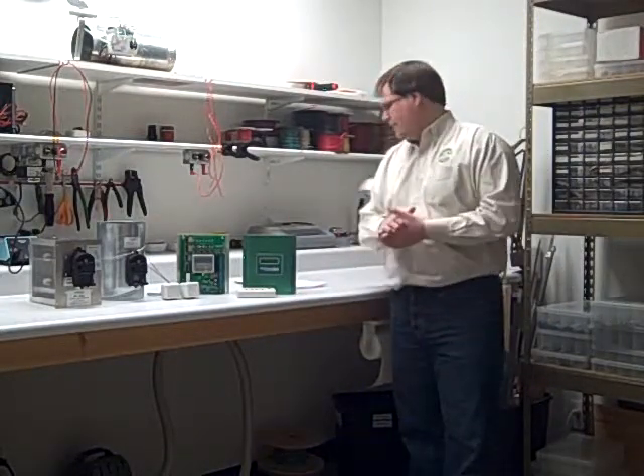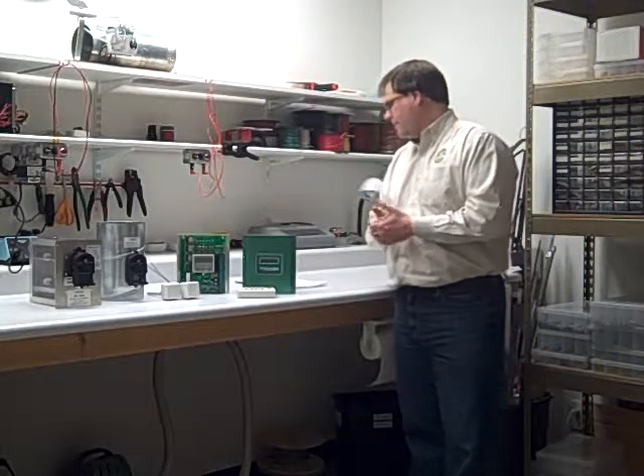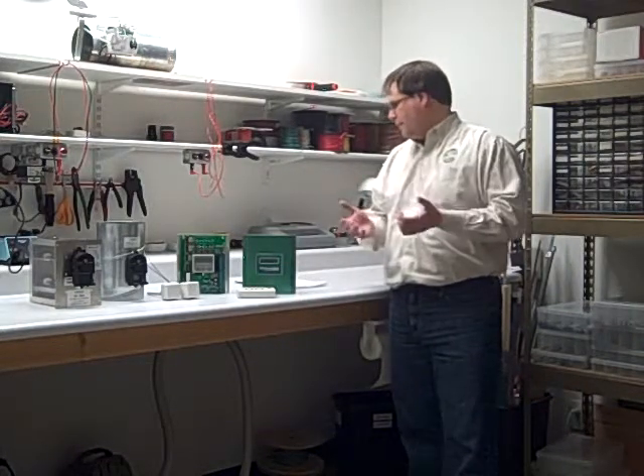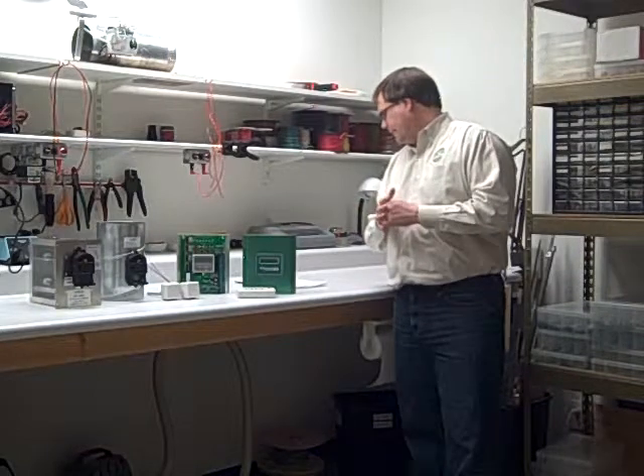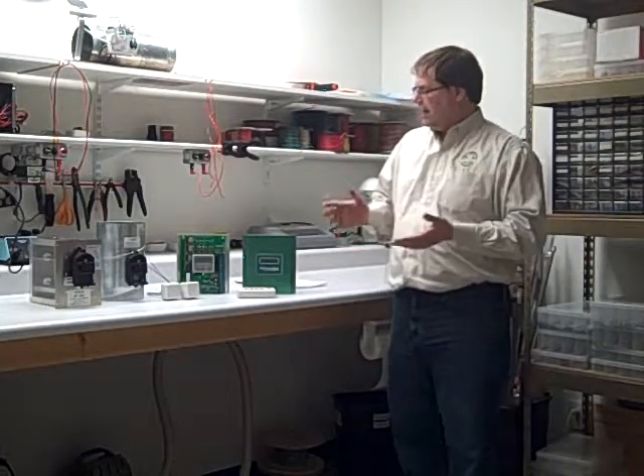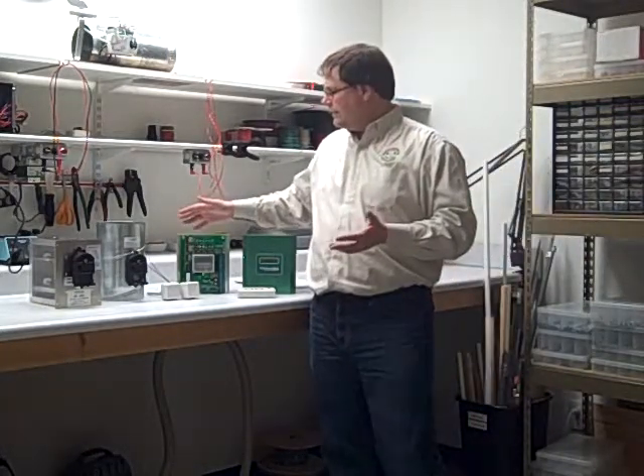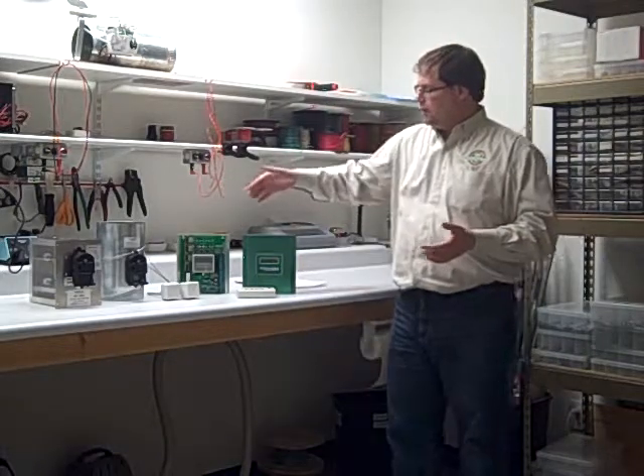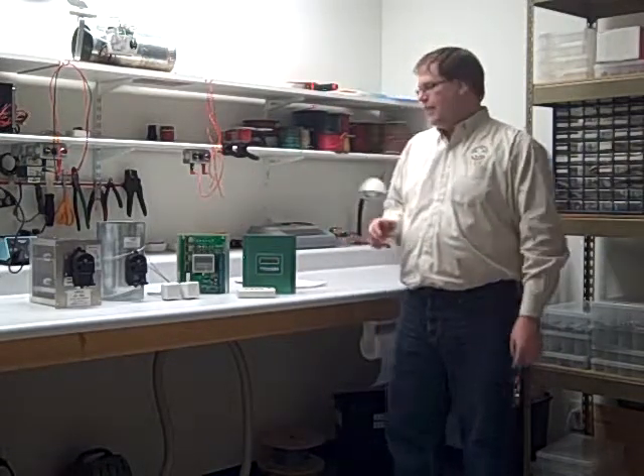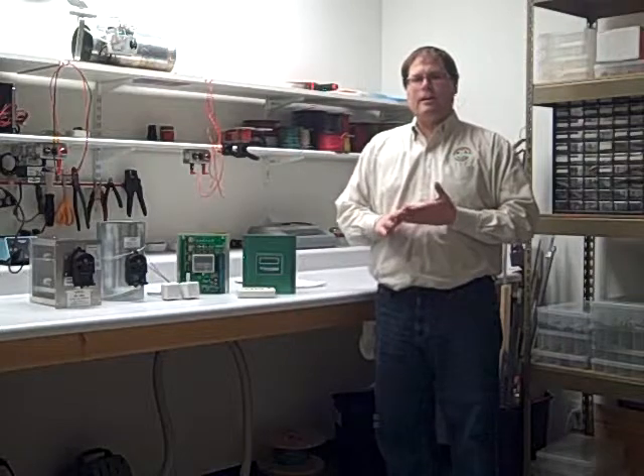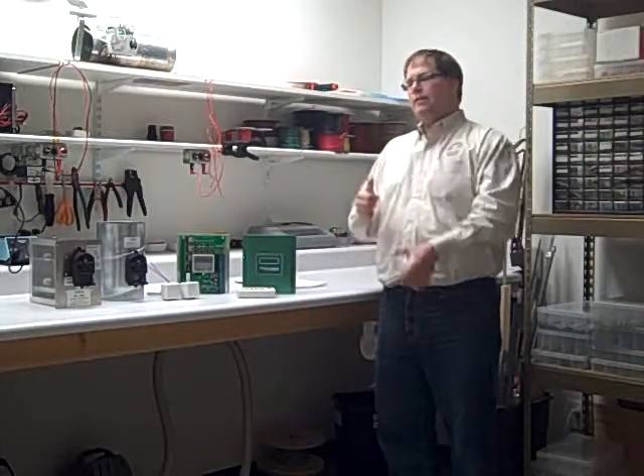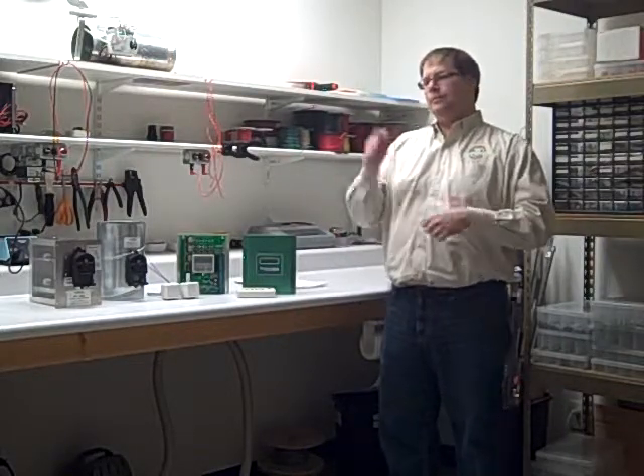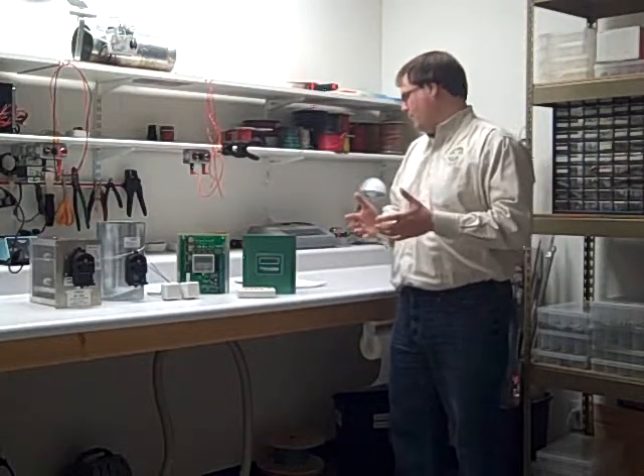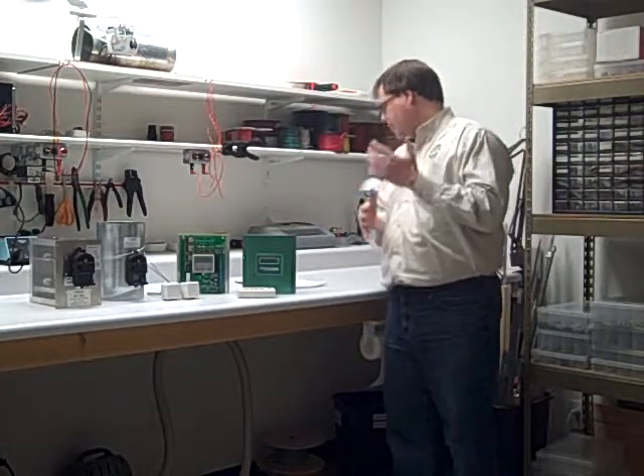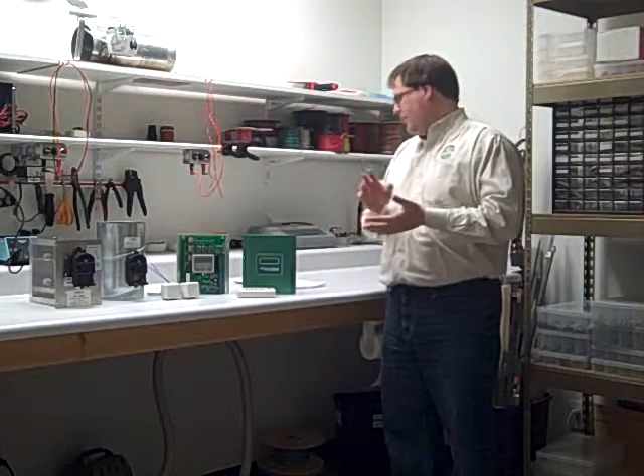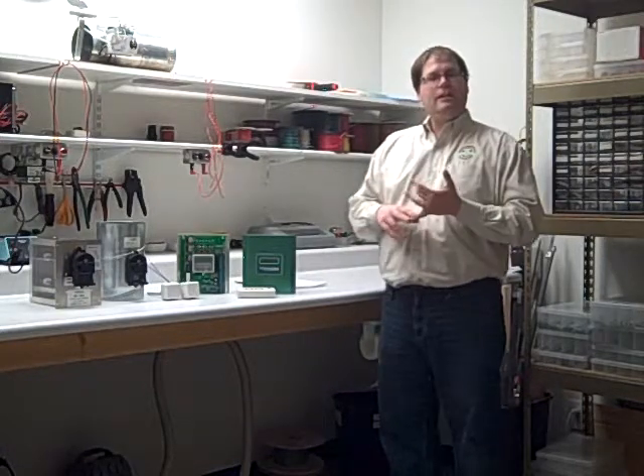We've talked about the additional safety features with the return air sensors. We've talked about fuse protection. It also has a lot of the features you know if you've used our regular Z-600. We've incorporated a lot of those features, like the timeshare option. In other words, if you want to make sure that we don't get locked into heating or cooling because someone's playing with the thermostats, it's got the timeshare option. It's got adjustable minimum run time, adjustable minimum off time, ventilation by zone.